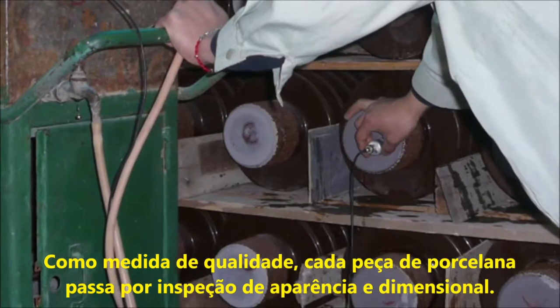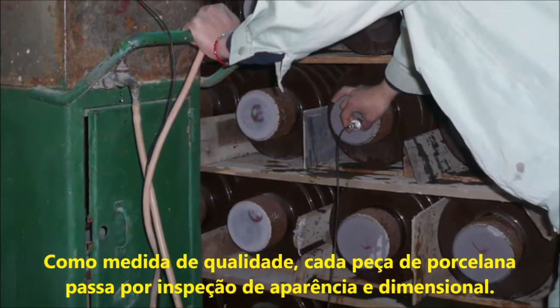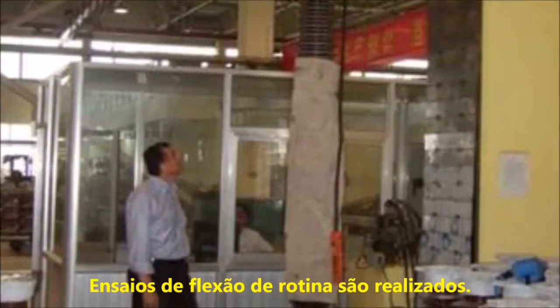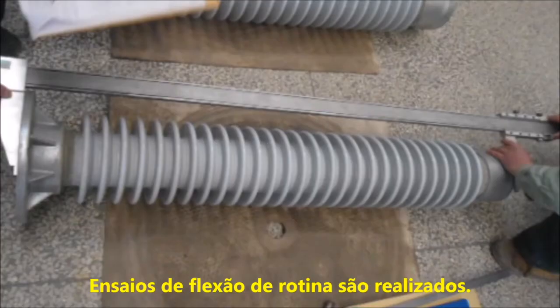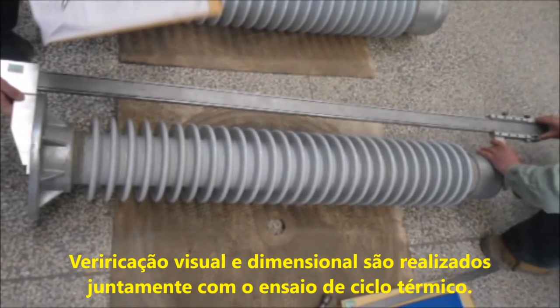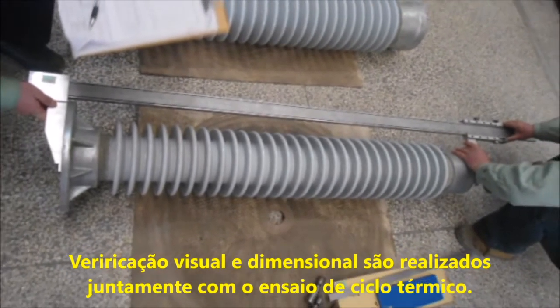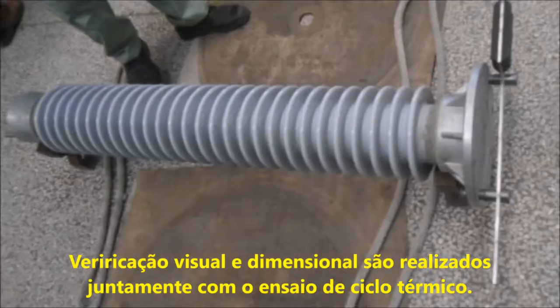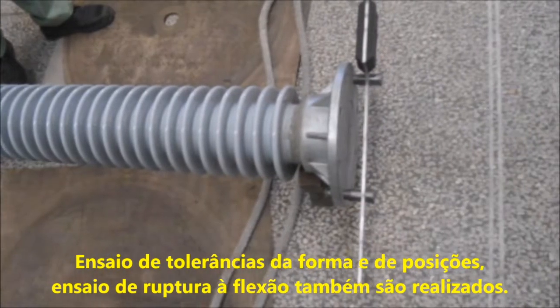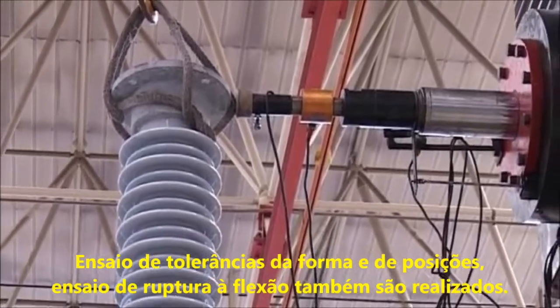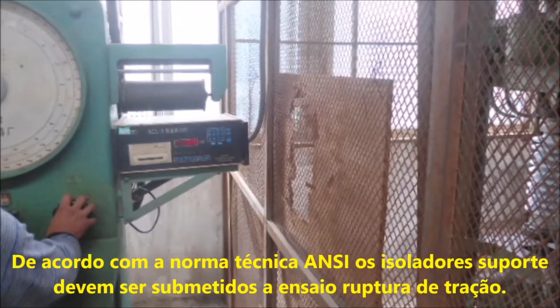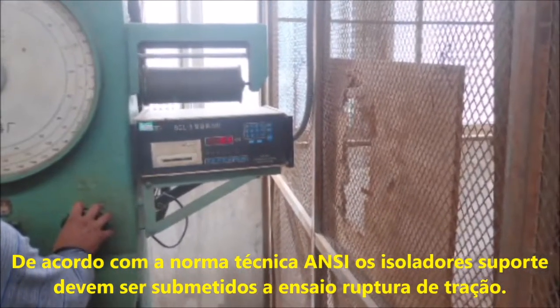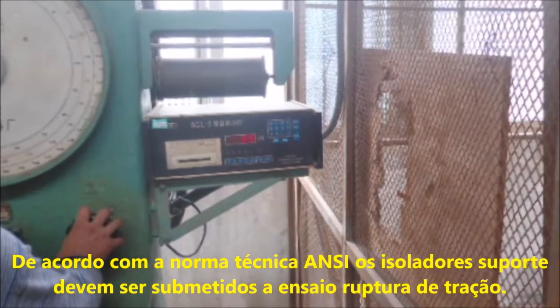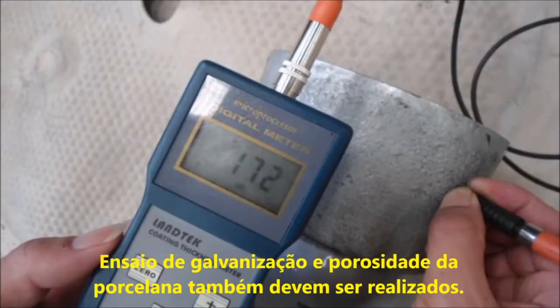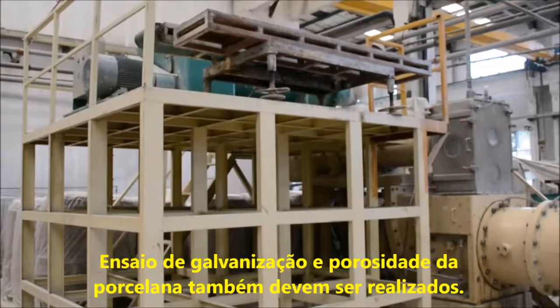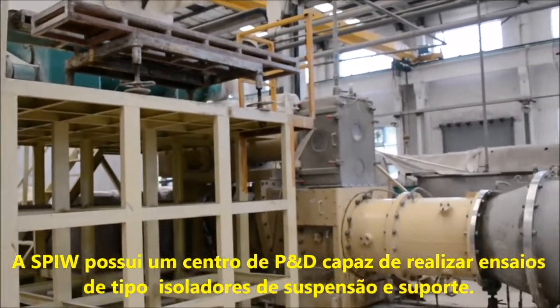Each piece of porcelain receives appearance and dimensional inspection. Routine bending load tests are conducted. Product spot checks for appearance and dimensional quality along with temperature cycling tests are conducted. Form and position tolerance test. Bending failure load test. According to the ANSI standard, station insulators undergo tensile failure load test, galvanizing test, and porcelain porosity tests.